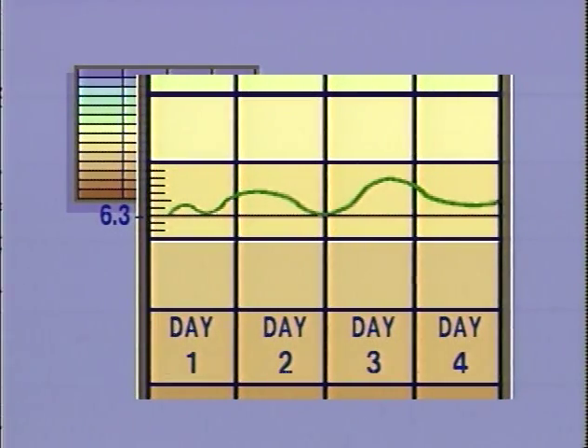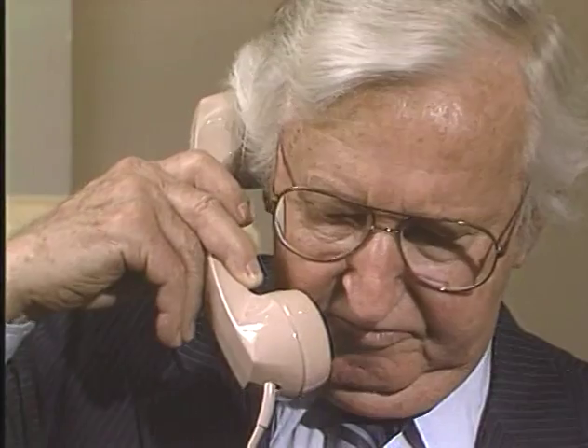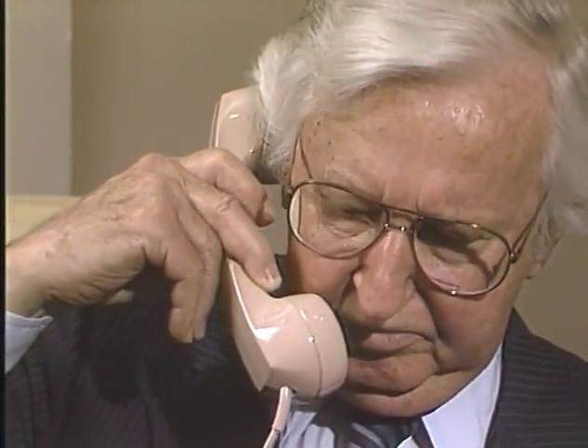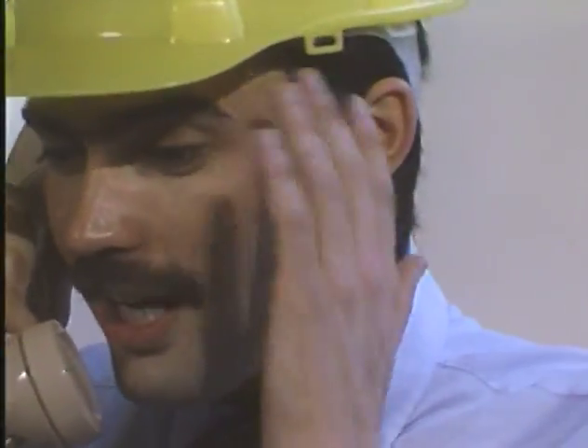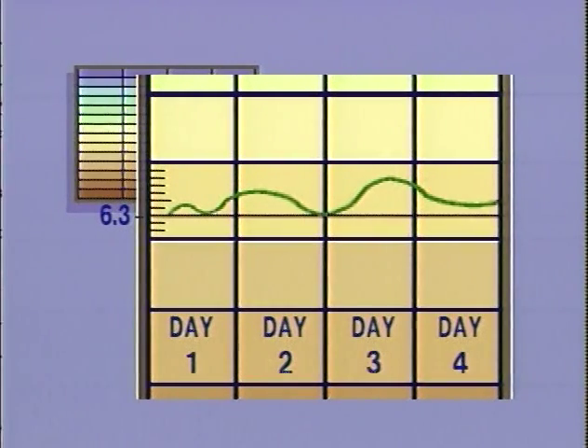On the 3rd day, however, the pH varied between 6.6 and 6.8. Even more acid had been added than on the previous days, so there appeared to be nothing wrong with the feed-forward controller. But somehow this increased amount still wasn't enough to bring the pH down to 6.3, or even to an acceptable 6.4. The company president was not pleased with the young engineer or his bright ideas. So the enterprising young man consulted the company chemist, who quickly explained what went wrong. The concentration of the acid additive varied. There was no way to account for the variation, so a change in the acid concentration resulted in a pH level that was out of specification.